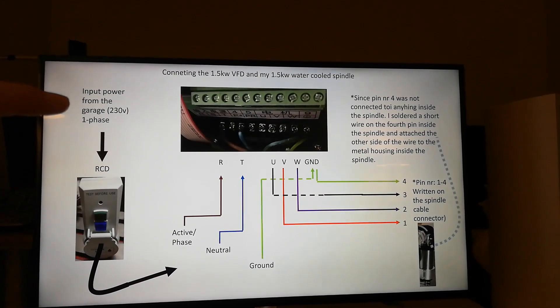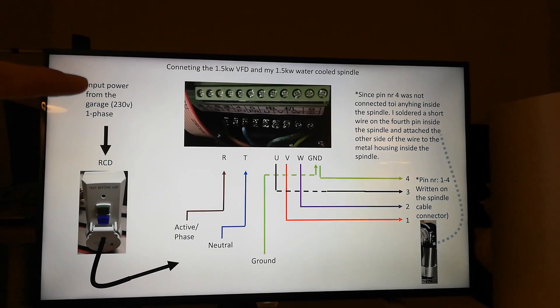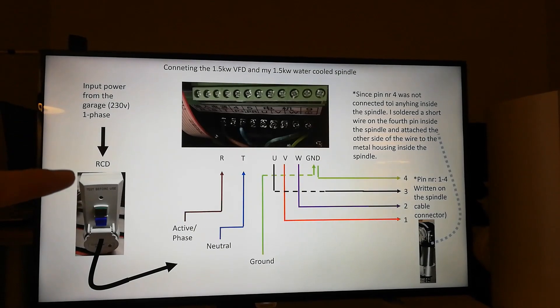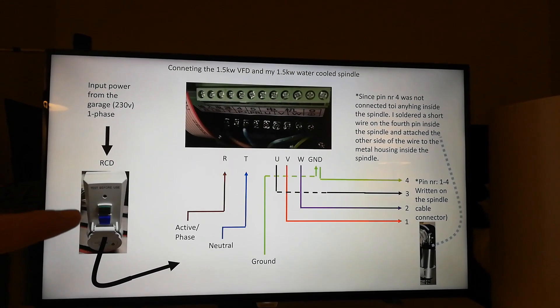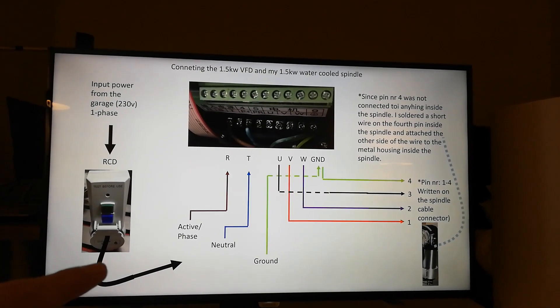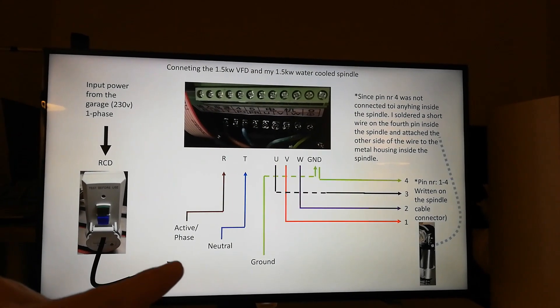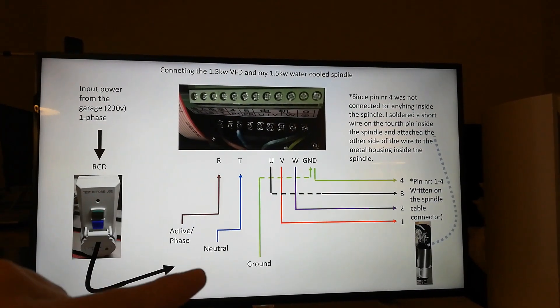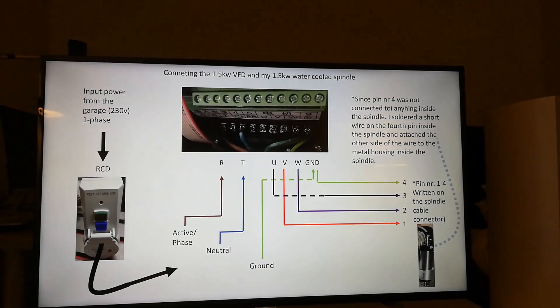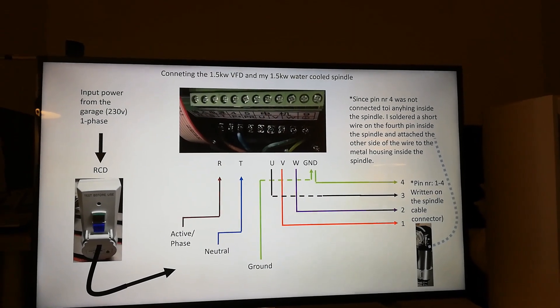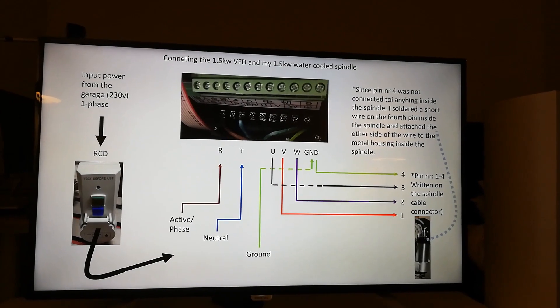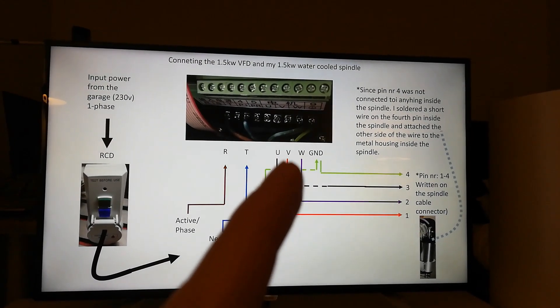If we start up here I have 220 to 230 voltage in the garage, one phase. Since the garage didn't have an RCD I bought one just to be safe. From the power here I connected the phase or active to R, neutral to T and ground to ground. That's pretty straightforward. To connect the spindle to the VFD I connected pin number one to V, pin number two to W and pin number three to U.